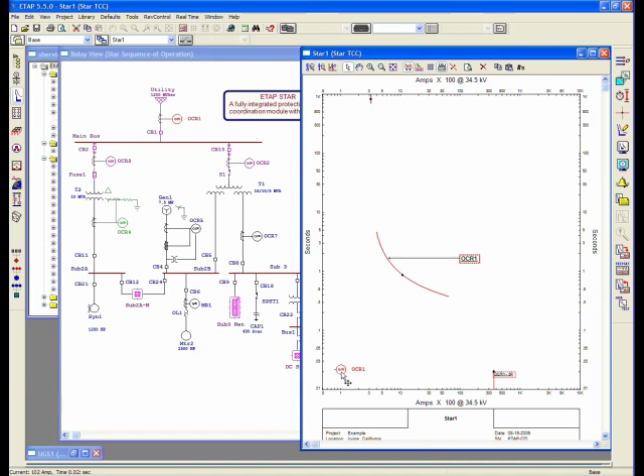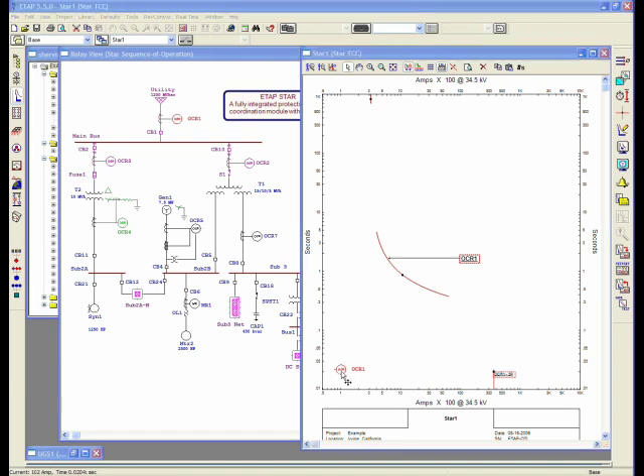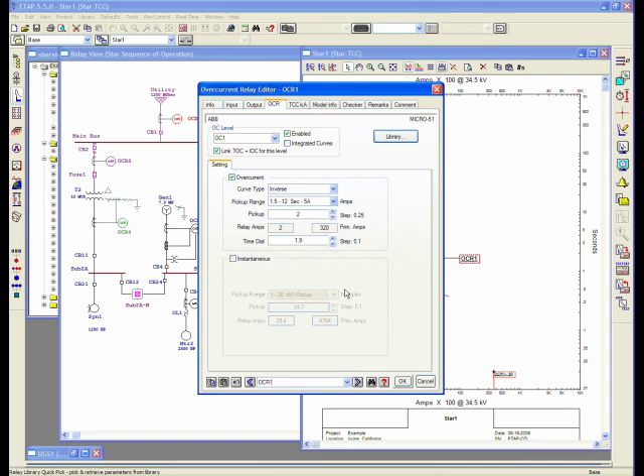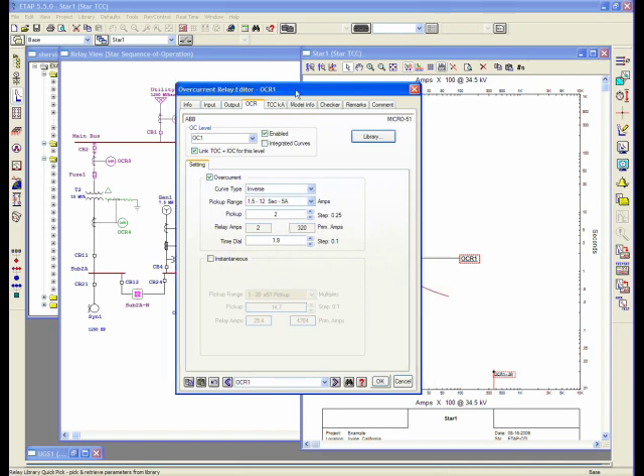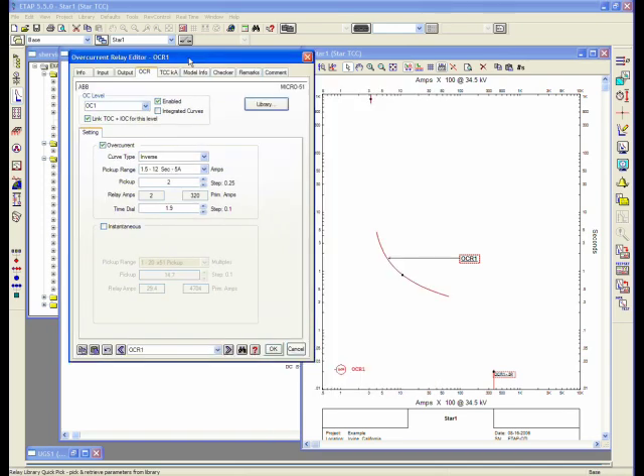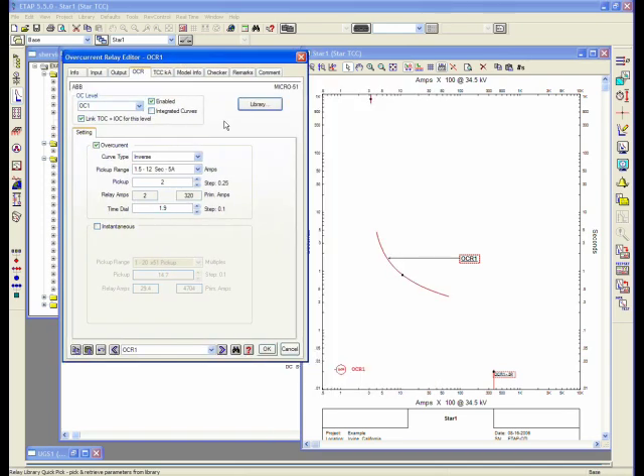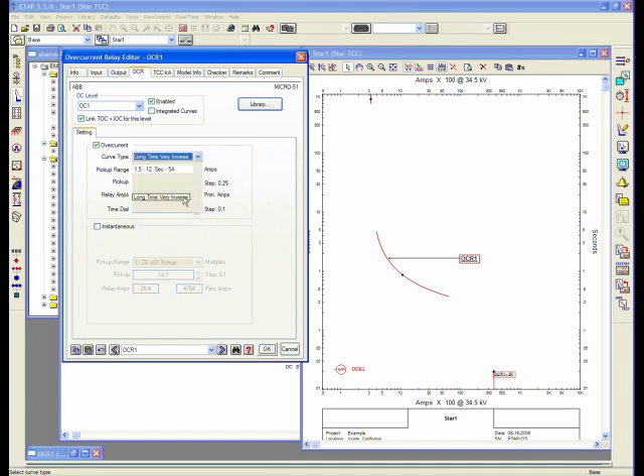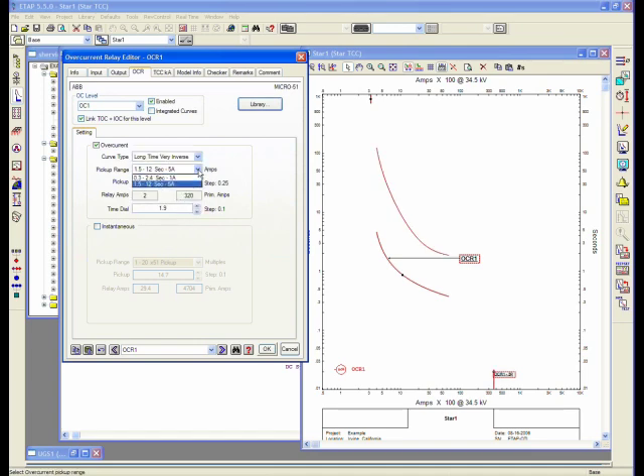If I were to double-click on the relay, it would launch a relay editor, which consists of several pages. The page that it would automatically go to would be my over-current page, since it's an over-current relay. Here I can also select a different type of curves. For example, I can select a long-time inverse. I can select the different ranges available for this model. Micro 51 has two models available within it.